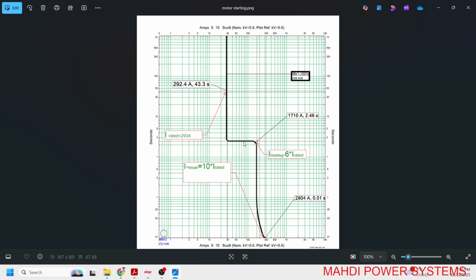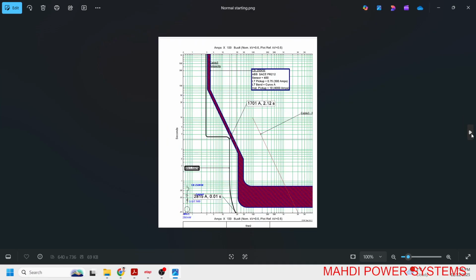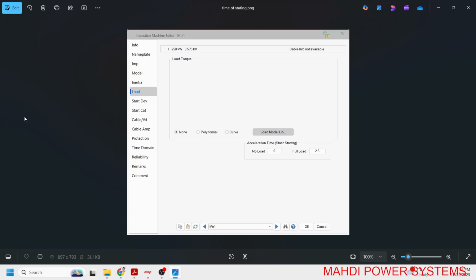After the starting phase, once the motor reaches the rated speed, the current drops. That's the drop of current. We go to the left and the current drops, and the motor settles at the normal operating current. This is the rated current of the motors, 293 amp. Now let's look at this sketch.